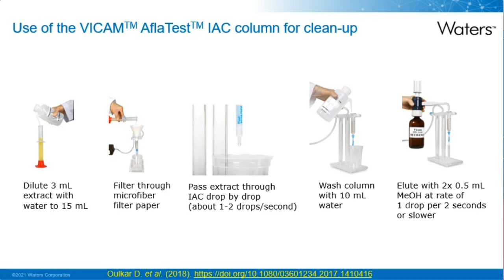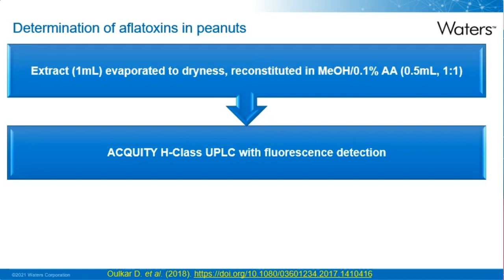The mycotoxin in the extract binds to the antibody. Impurities are removed by washing the column with water or an aqueous buffer, and then the mycotoxins are dissolved with water-miscible solvents such as methanol. The extract is evaporated to dryness and then reconstituted in the mobile phase prior to analysis with UPLC with fluorescence detection. The combination of cleanup using immunoaffinity cartridge and the determination by UPLC with fluorescence detection has been a prerequisite step to achieve the desired sensitivity and selectivity needed to check compliance with the strict aflatoxin regulatory maximum limits.